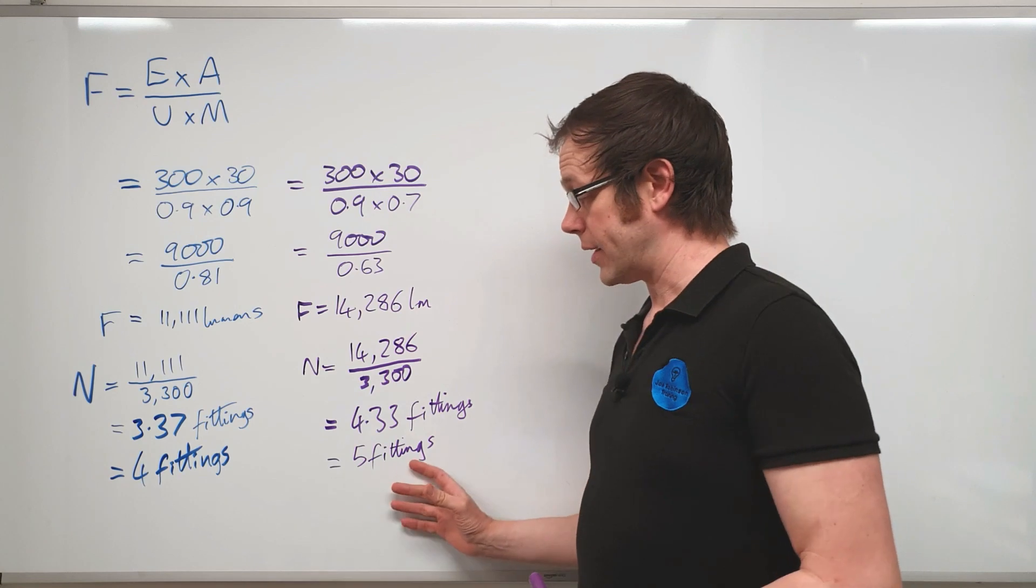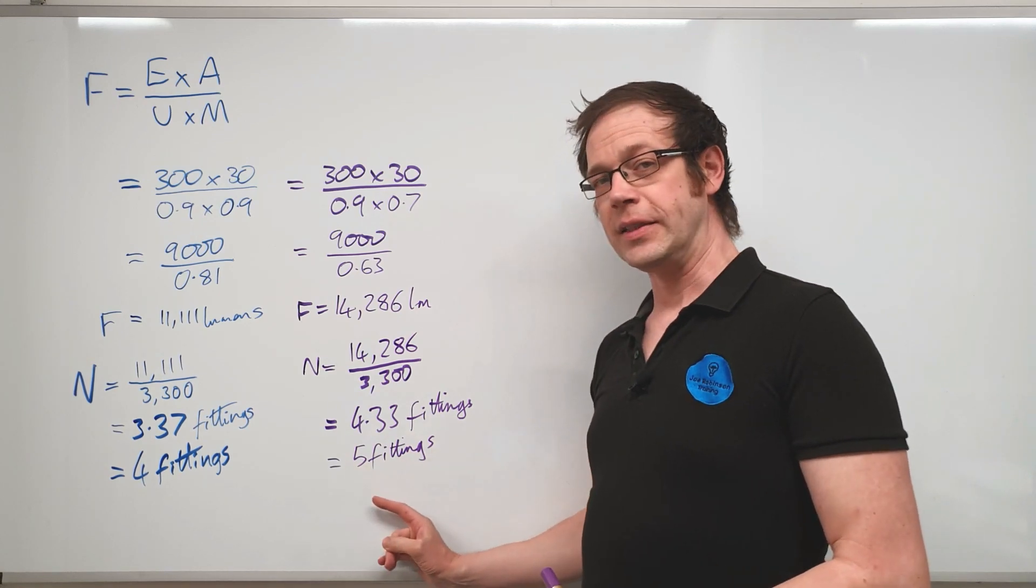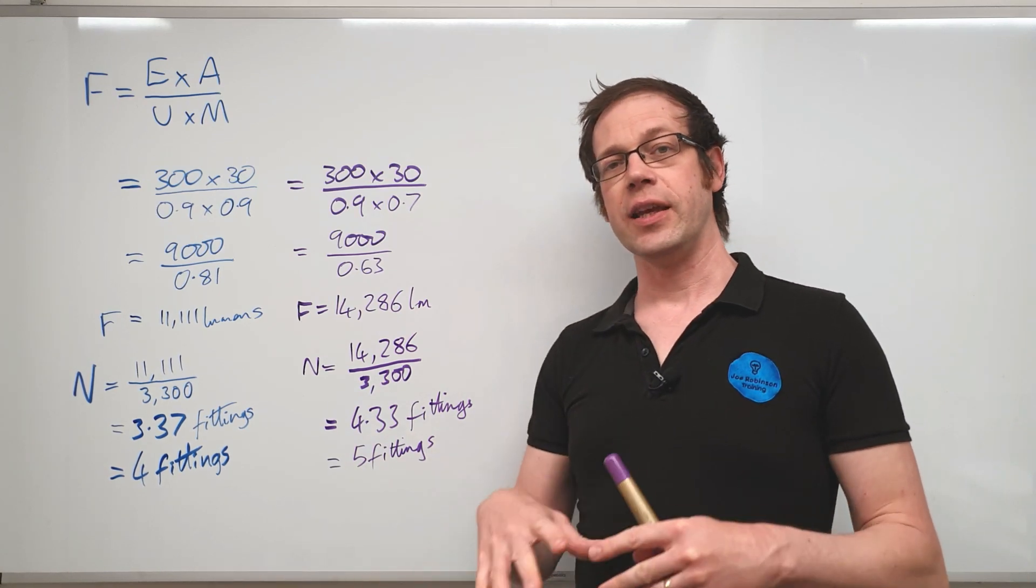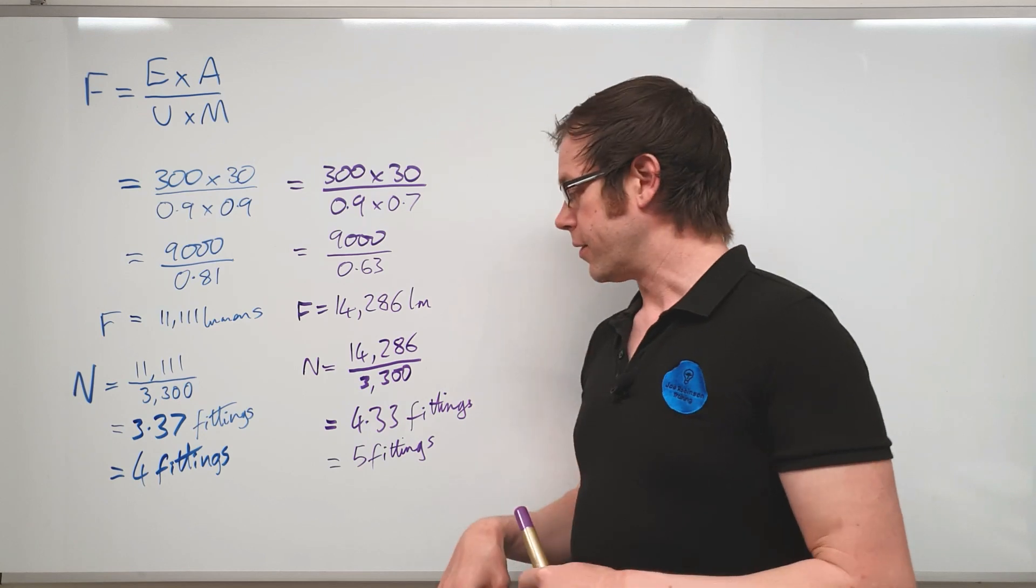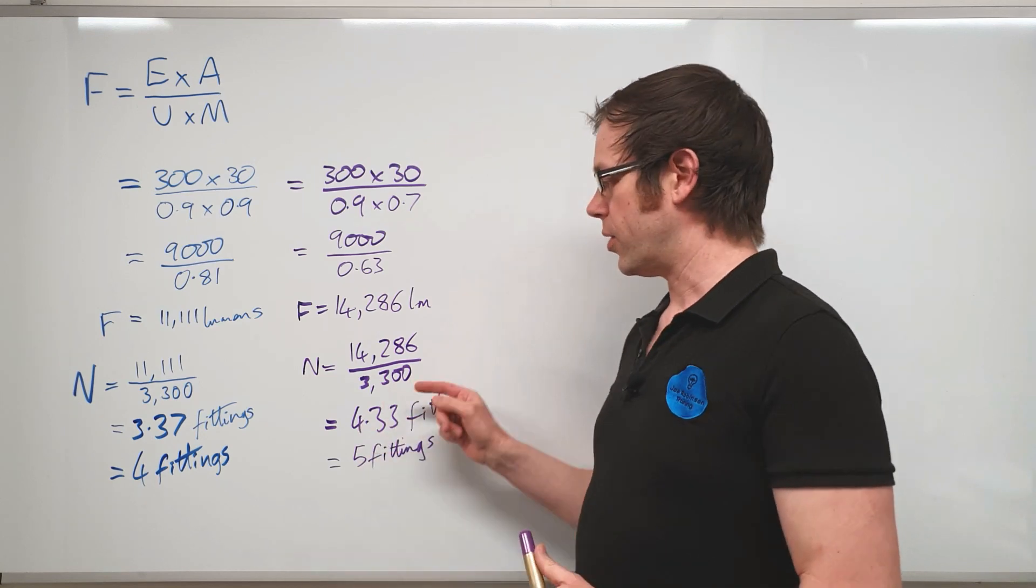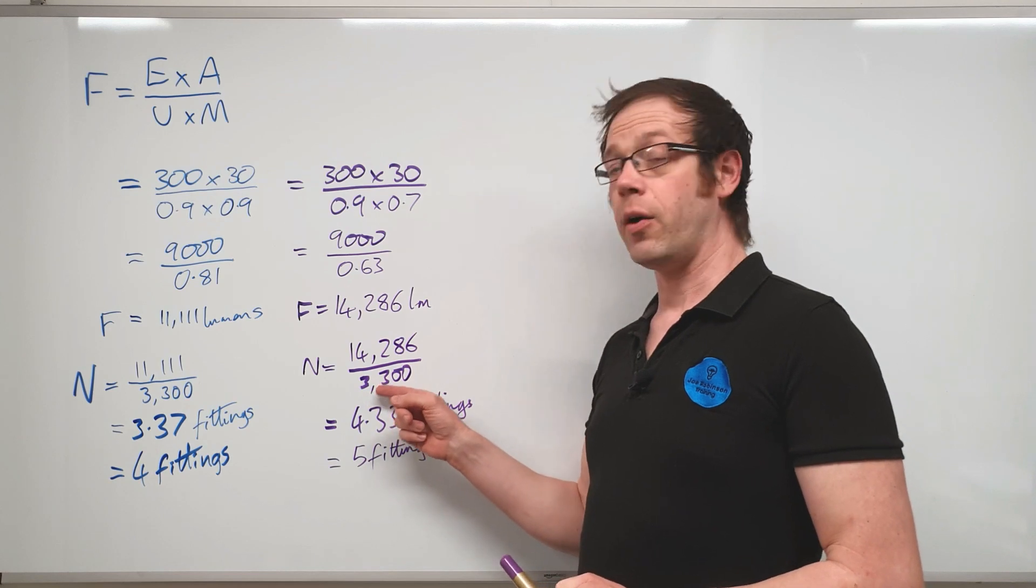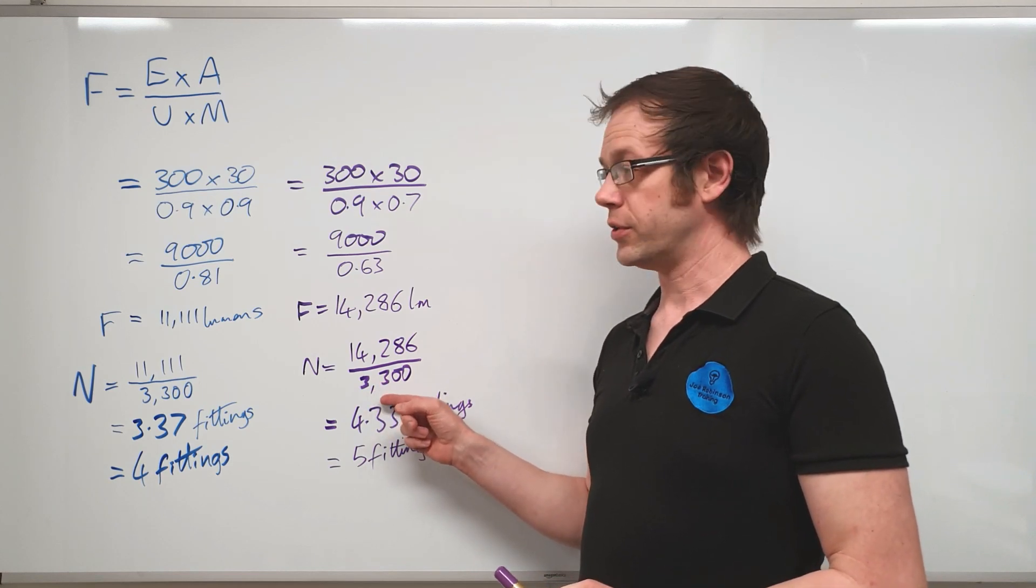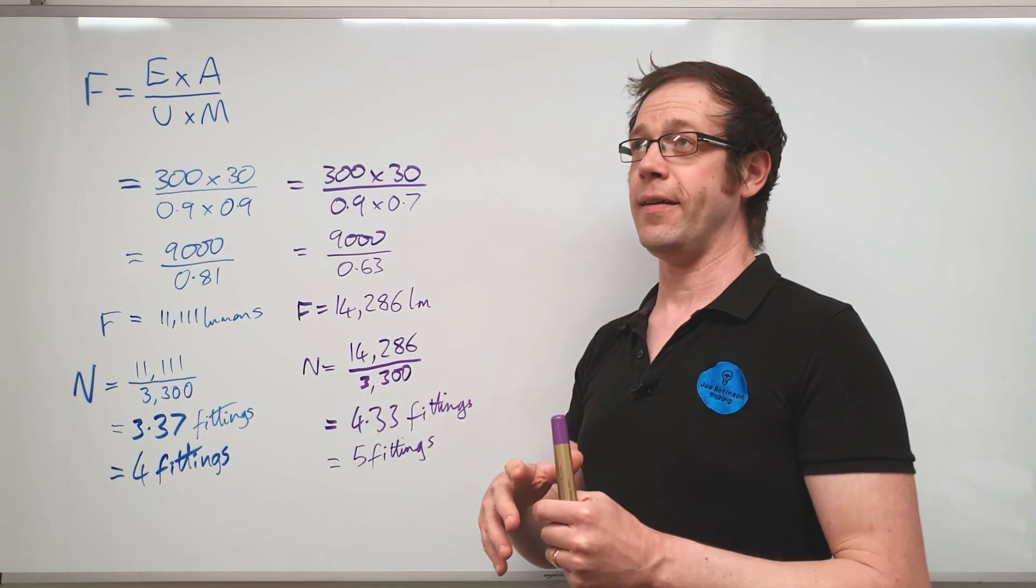If you've got a square room or a rectangular room, it's going to be quite difficult to space out five fittings so that you get a nice spread of light. So what you might end up doing in this case is trying to figure out if there's a fitting that has a slightly lower value of luminous flux.